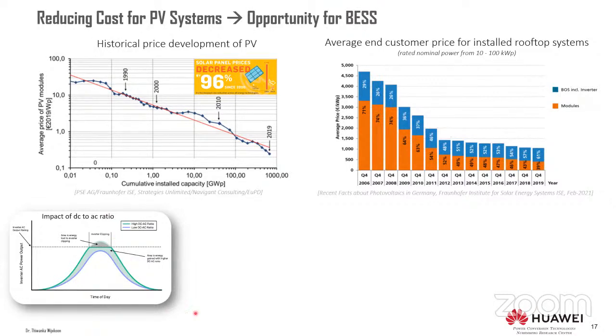What does this mean? DC means the amount of PV panels you put on the DC generation side, and AC means how much power you feed into the AC grid. If you have more panels than you can feed into the grid, the DC-AC ratio goes high, usually higher than 1. What happens is that with this higher DC to AC ratio, at certain points you have to clamp because of the limitation of your inverter. However, you still get more generation compared to a lower DC-AC ratio. This could be advantageous if panel prices are low.